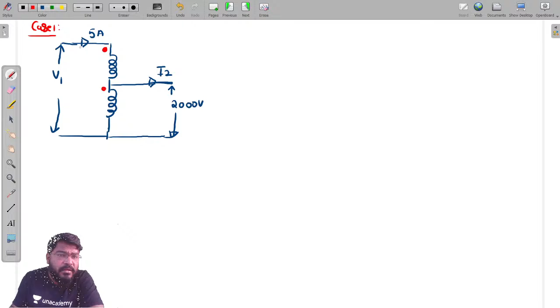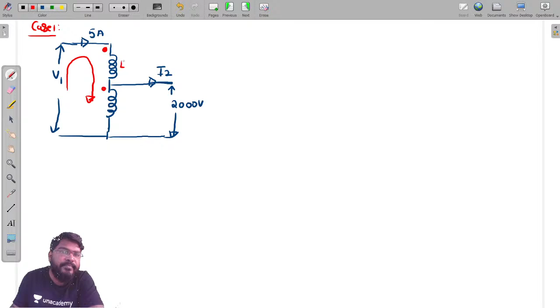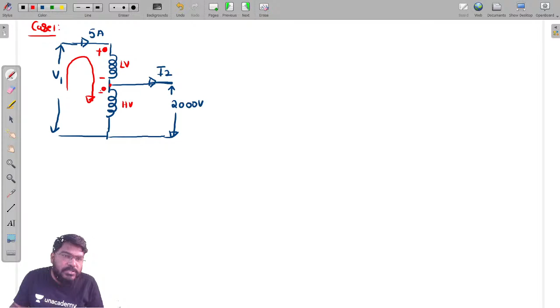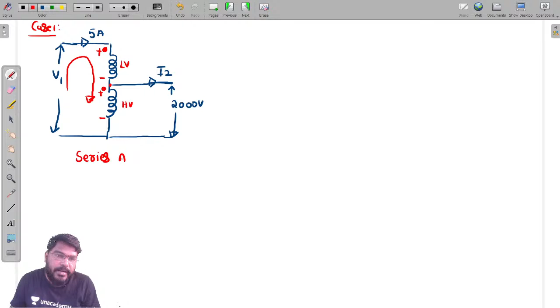Then what is V1, tell me. First tell me which connection is here. This is in a loop here, in this loop. So here current is entering at the dot position of the coil. This is the LV winding and this one is the HV winding. So here current is entering, this one is plus with respect to the other terminal. So these two windings are connected in series additive polarity connection. So here it is the series additive polarity of auto transformer.